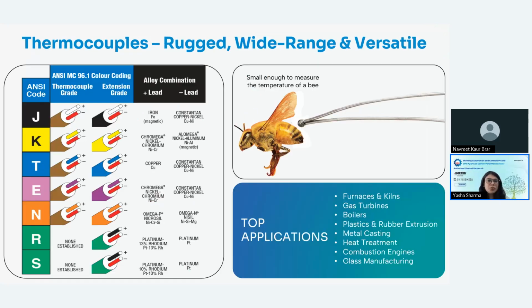Next, let's move to our next sensor, the thermocouple. A thermocouple works on the Seebeck effect. Now I'll tell you what the Seebeck effect is. When two dissimilar metals are joined to form a junction, and there is a temperature difference between the hot junction and the cold junction, a small EMF is generated in millivolts, and that small EMF is mapped to the temperature. That's how a thermocouple works.